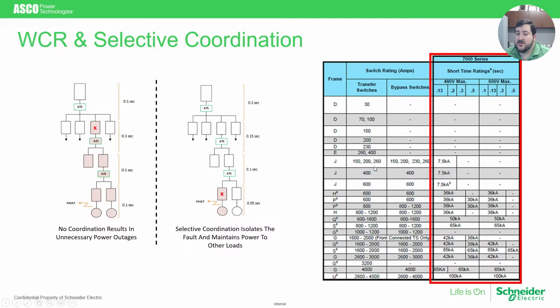The transfer switch's WCR rating is then important because the WCR rating is composed of two numbers. It's composed of a duration of time as well as a level of fault current. So for example, on this table, we can see that this J-frame ATS, or better said, this H-frame ATS down here at 480 volts can withstand 36 kA of current, 36 kiloamps, for a duration of 0.3 seconds.